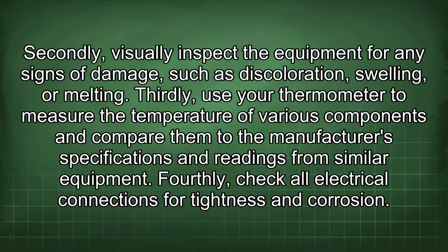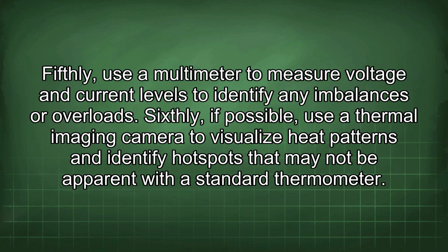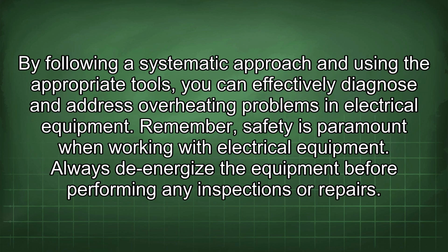Fourthly, check all electrical connections for tightness and corrosion. Fifthly, use a multimeter to measure voltage and current levels to identify any imbalances or overloads. Sixthly, if possible, use a thermal imaging camera to visualize heat patterns and identify hotspots that may not be apparent with a standard thermometer. By following a systematic approach and using the appropriate tools, you can effectively diagnose and address overheating problems in electrical equipment.